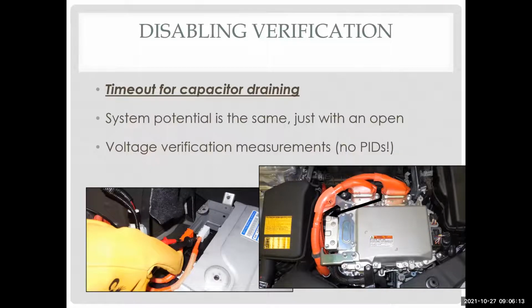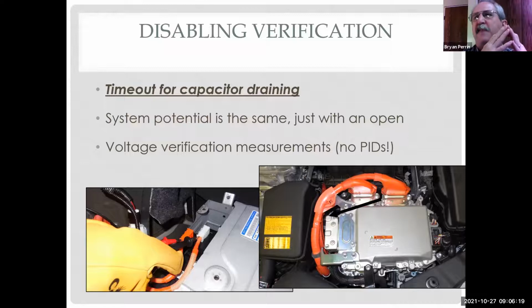Yes, Mr. Brian, how long does it typically take for the capacitors to discharge and drain? Normally about 5 to 10 minutes. It doesn't take that long on these. If they're huge capacitors, they're normally 2,700 microfarads, and there's 3 of them, and they're pretty good size. I have some of them—you can see I have an inverter in the classroom and you can see the capacitors. They're pretty good size, but they do normally discharge in about 5 to 10 minutes. So although they're big, they don't hold their charge very long.